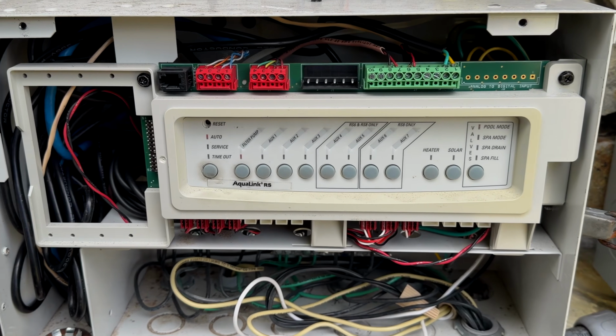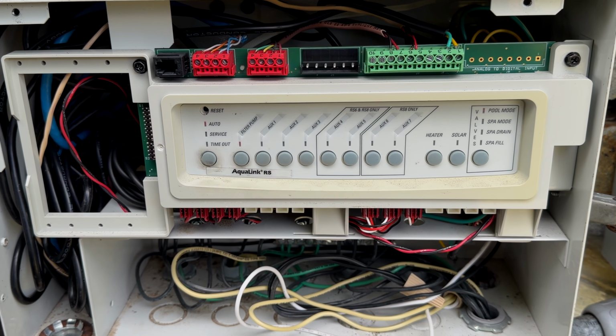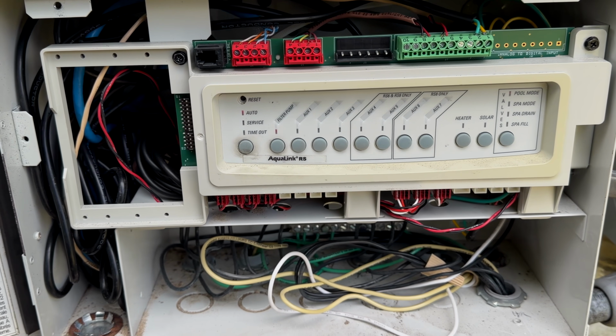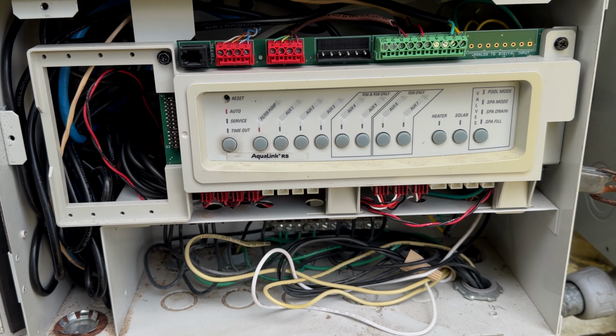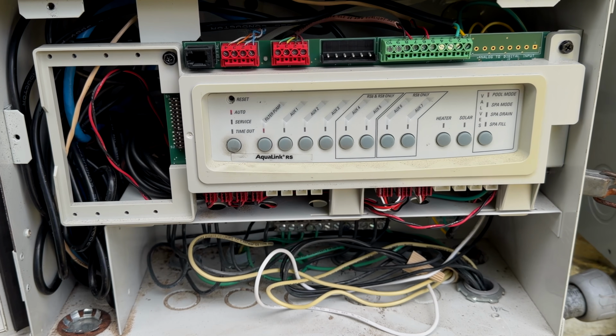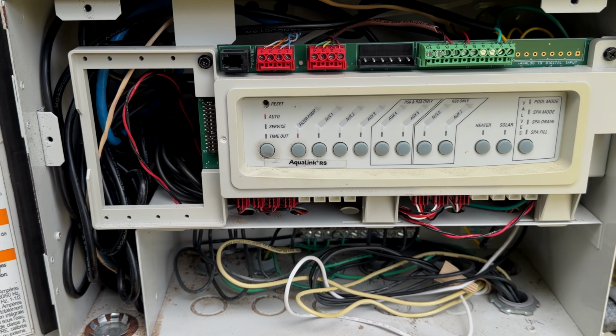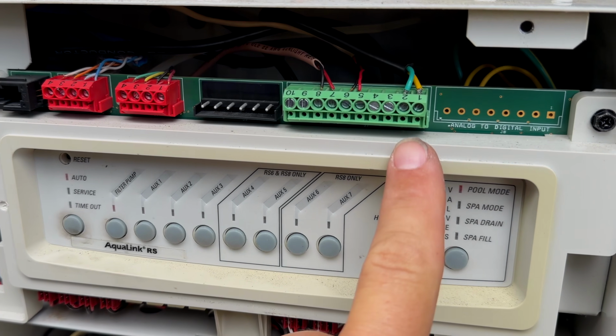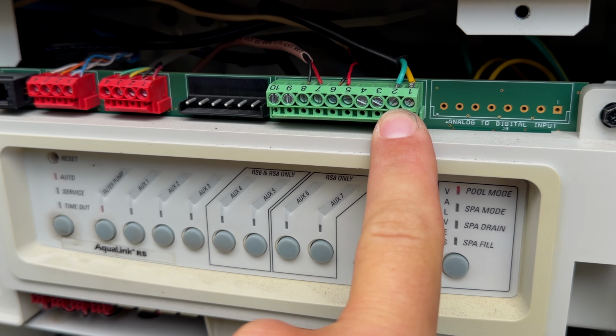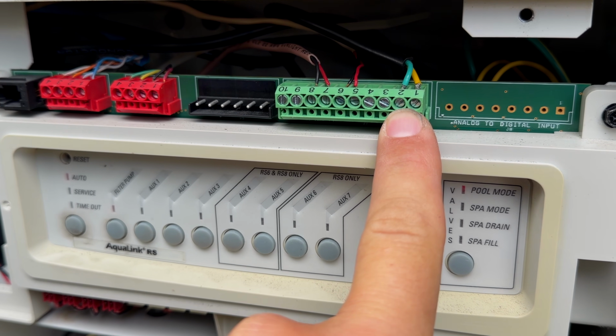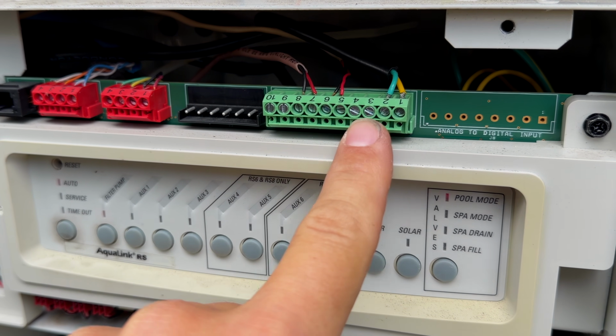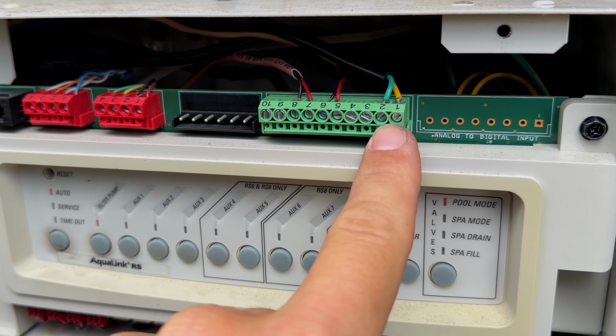So the automation system here at this property is a Jandy AquaLink RS. So if you remember those top 2 contacts in the heat pump for the pool spa T-stat, where does that go? Well, that goes on any automation system to the low voltage heater port, which on this automation system is on this green 10-pin bar on spots 1 and 2.